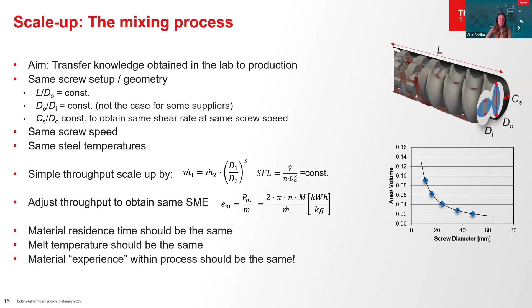On the next slide, the different sizes of Thermo Fisher Scientific twin screw mixers are presented. The smallest is the tabletop Energy 11 with 11 millimeter screw diameter. Besides that, also larger twin screw mixers with 16 millimeter and 24 millimeter screw diameters are available. This portfolio covers a material throughput range from 100 milliliter per hour up to 20 liter for battery slurries. Unlike production scale twin screw mixers, they are easily operated by just one person, require very small sample volumes, and are scalable to larger sizes.